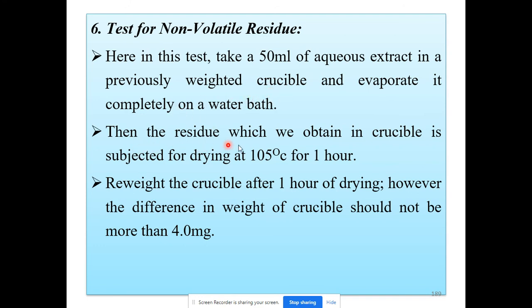The residue obtained after complete evaporation is subjected to drying at a temperature of 105 degrees Celsius for a period of 1 hour. After 1 hour, reweigh the crucible. The difference in weight of the crucible before and after drying should not be more than 4 mg. If the difference is not more than 4 mg, the rubber closure passes the test for non-volatile residue.